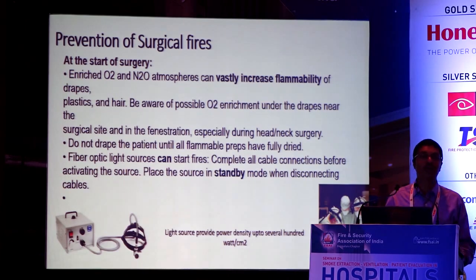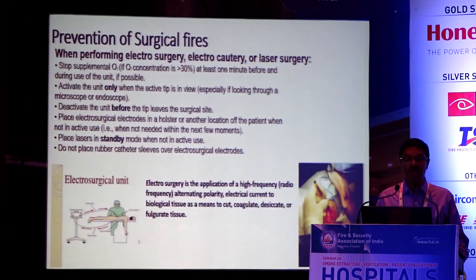The biggest challenge is with the electrosurgical system, the cautery machine. With the cautery machine you are using RF current for cutting and coagulation, and if it is not properly taken care of, it may lead to an issue. More than that, the biggest challenge is to convince the surgeons. This may lead to a problem, so please take some measures. We have some cases where there are burns, but the surgeons refuse to change their practice. This is one problem which we face, but we have to tactically handle it so that they do not make the mistake.